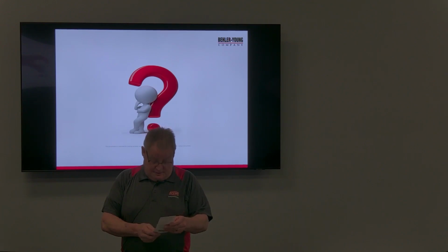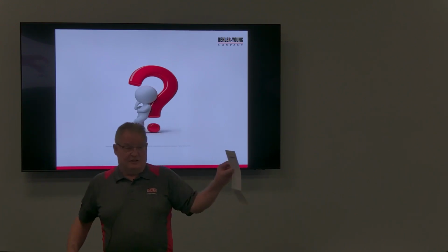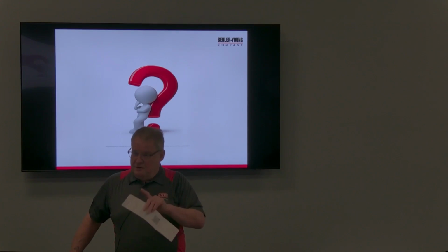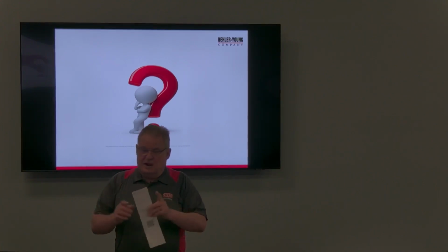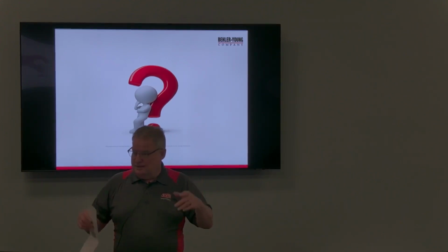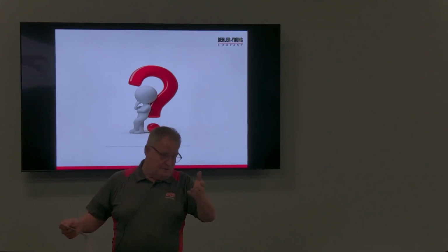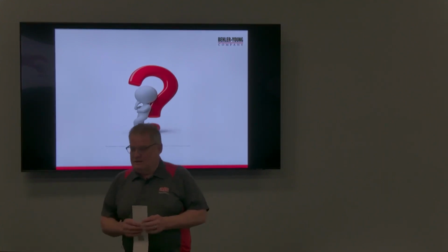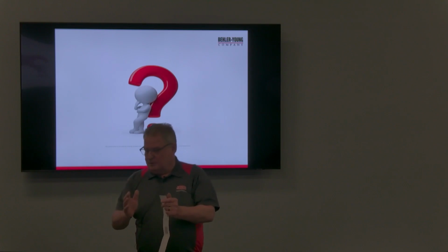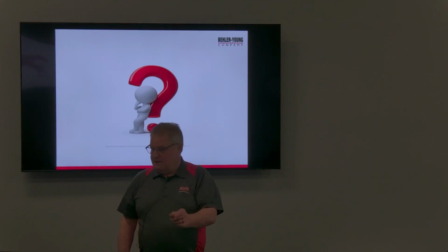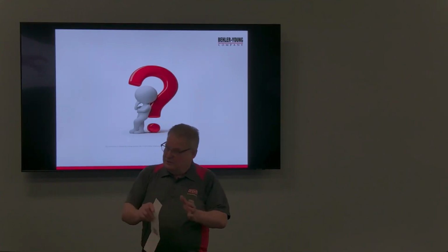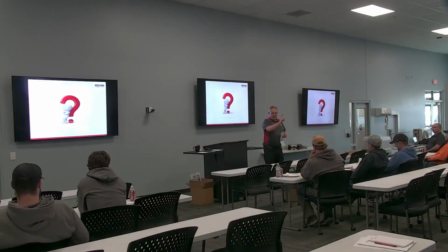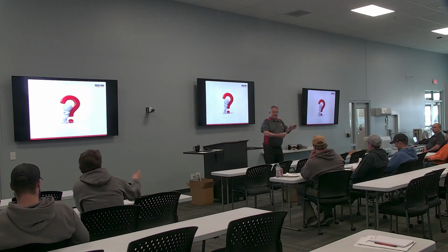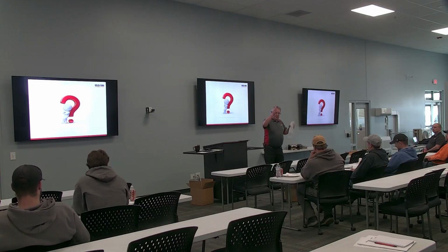R454B on this chart only shows a single boiling point. But the 400 numbers actually have 2. Some charts you'll see bubble point and dew point. Again, those who remember when 410 first came out, you remember these. It's the difference between when it begins to boil and where it finishes boiling. 410 had about a half degree glide, they called it, between boiling points. So generally we only have one number. 454B's got about a 2 degree glide. So when you look on some PT charts, it will list a bubble point and a dew point.